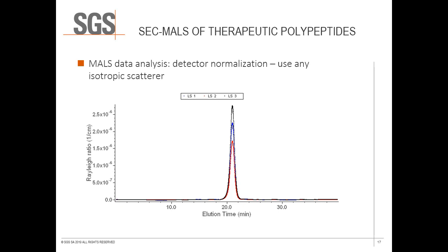Once baselines and integration limits are set for the standard peak, the software is commanded to normalize the MALS detector angles. And as you can see in this example, each detector voltage is multiplied by a normalization coefficient to match the voltage coming from the 90-degree detector.